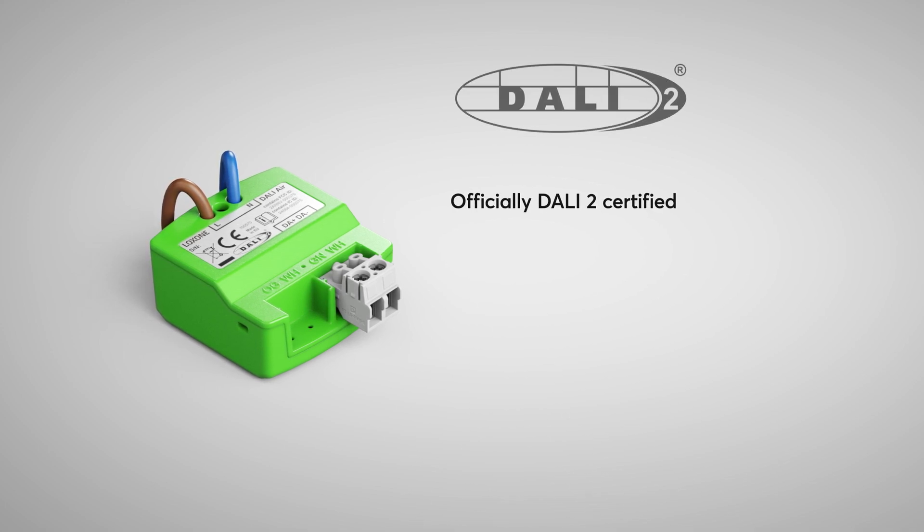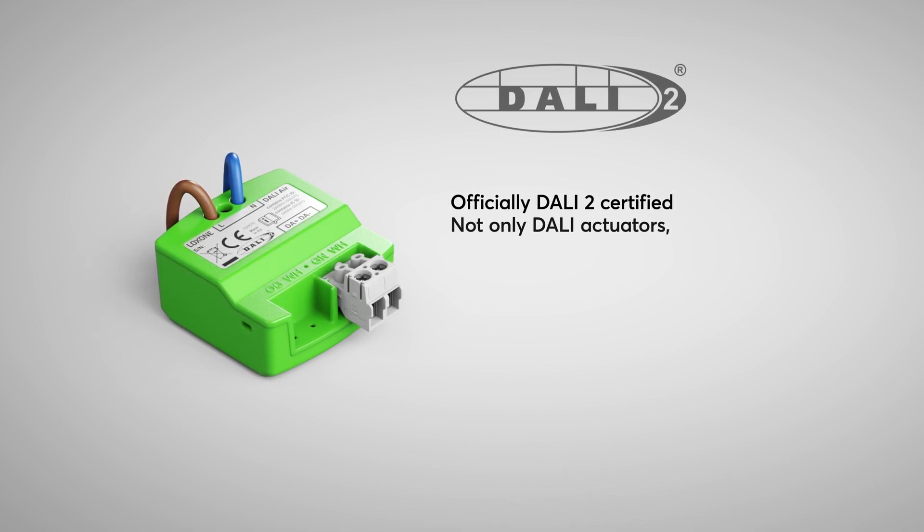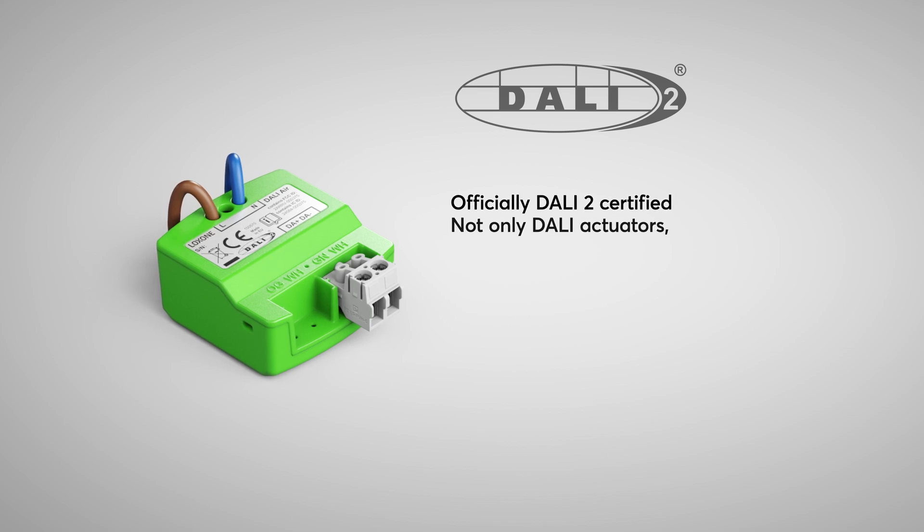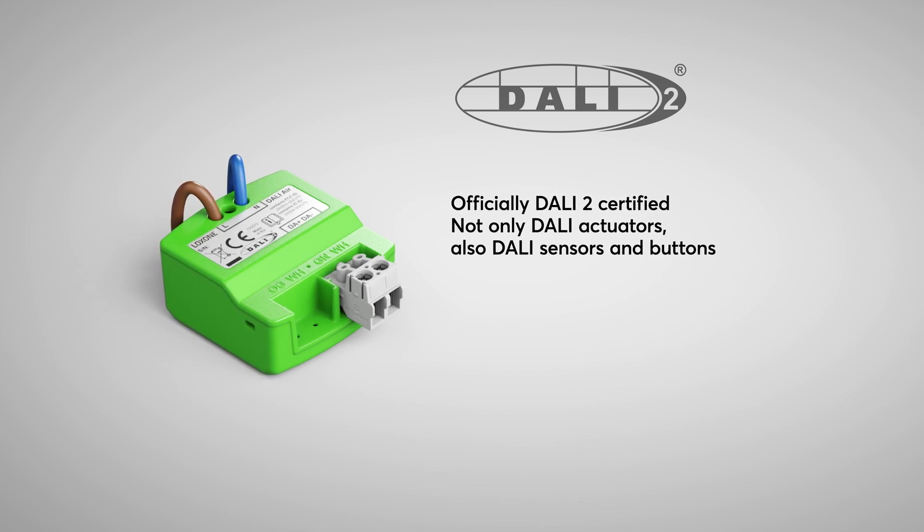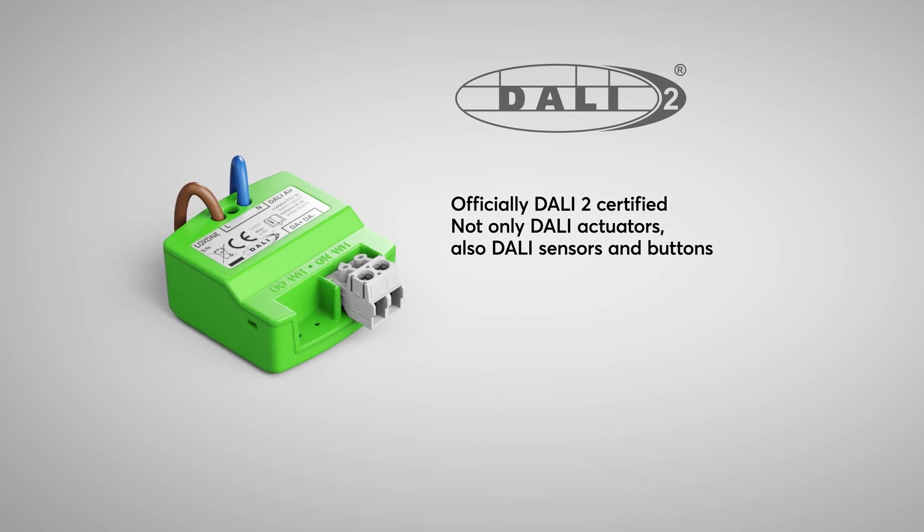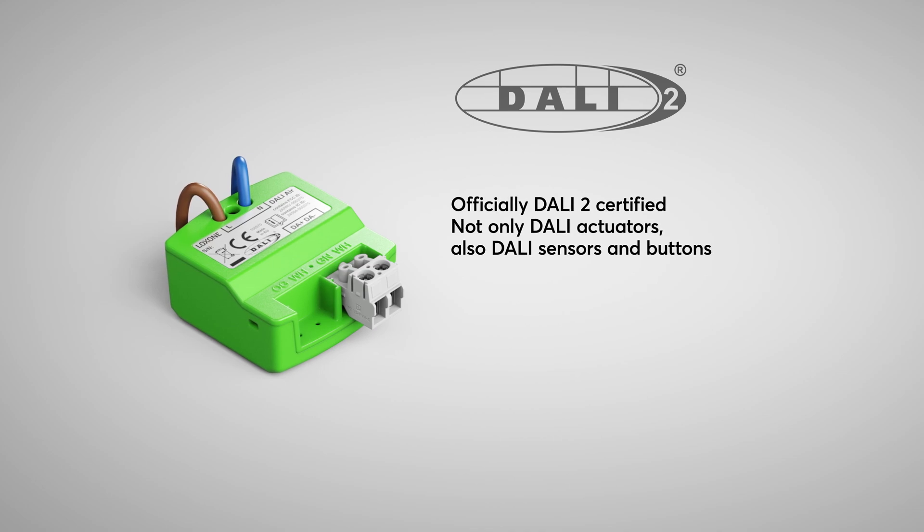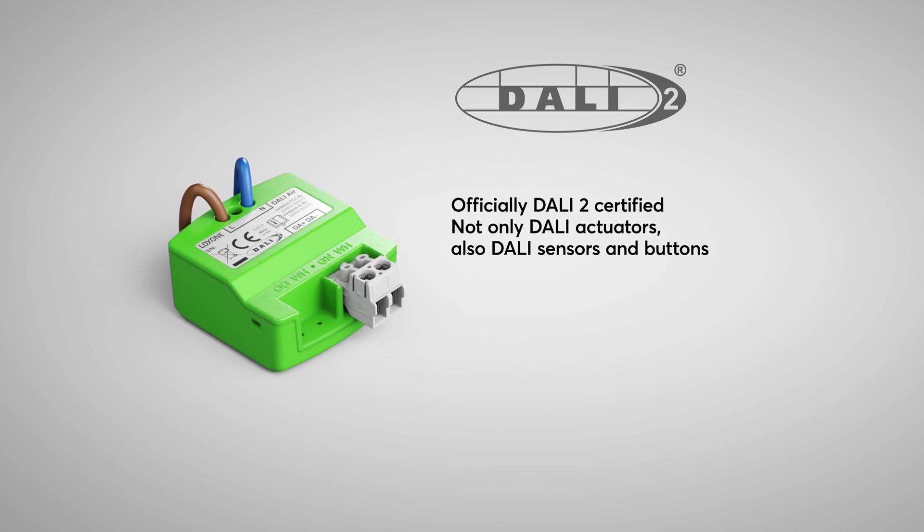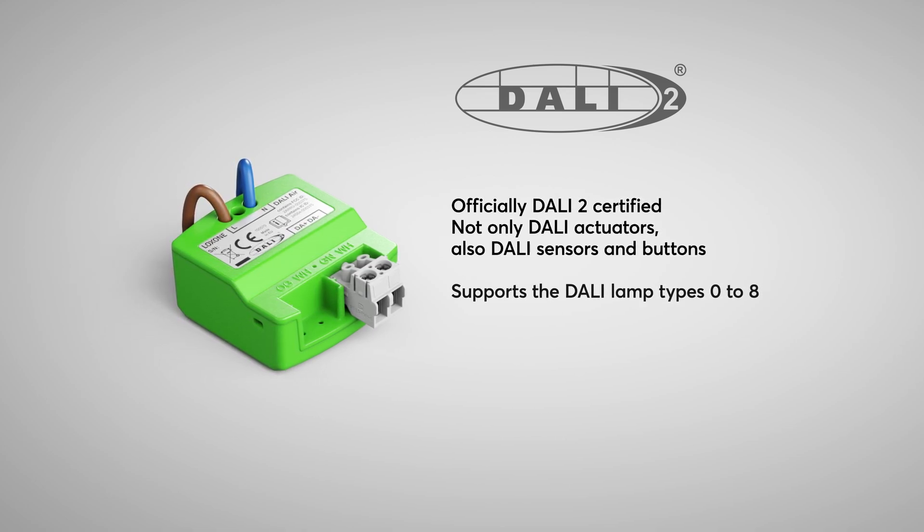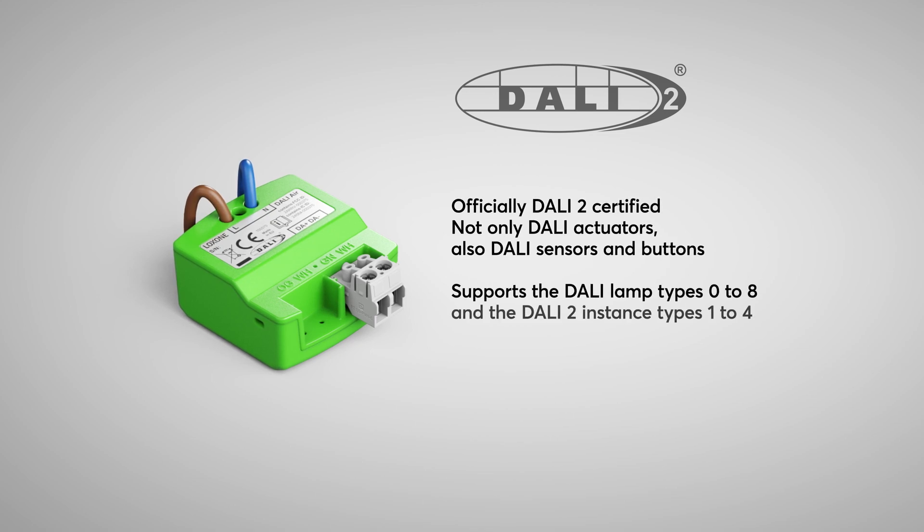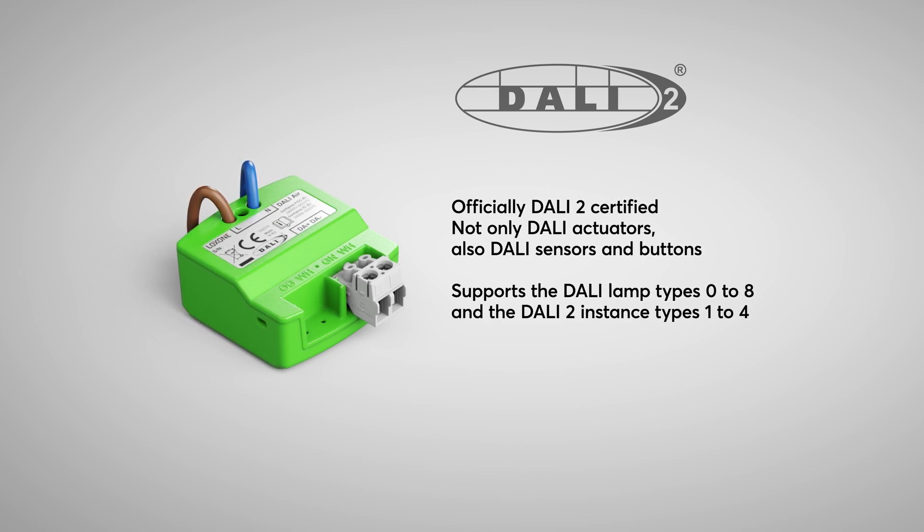This means not only DALI actuators can be taught in, but also DALI sensors such as a motion detector or a button can now be integrated into the Loxone ecosystem in no time. DALI Air supports the DALI lamp type 0 to 8 and the DALI 2 instance types 1 to 4.